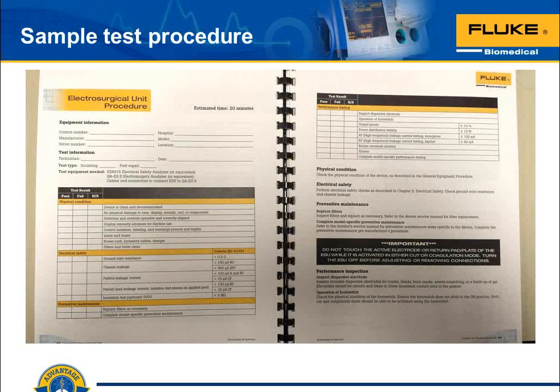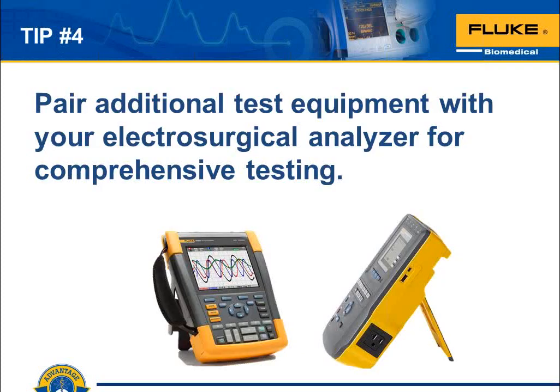So including cleaning, whatever steps you need, whether the manufacturer is recommending them or not, you need to be able to respond to how these medical devices are performing and what they're facing in your own facility. Let's go on to tip number 4. Pair additional test equipment with your electrosurgery unit analyzer for comprehensive testing. Now, what we're talking about certainly includes your regular electrical safety analyzer. That's an easy one. So you need that plus your ESU analyzer in order to really do all the testing that you need to do.